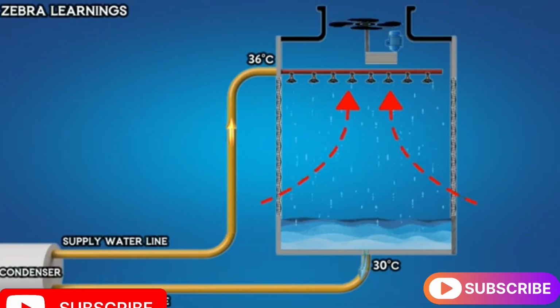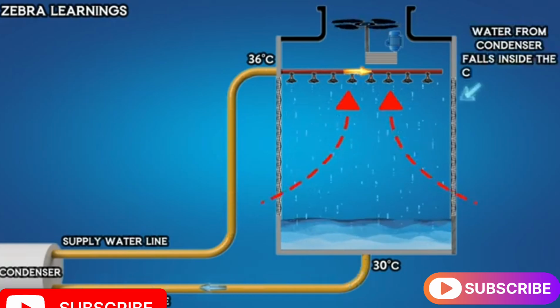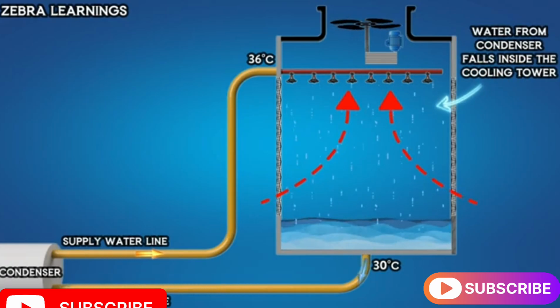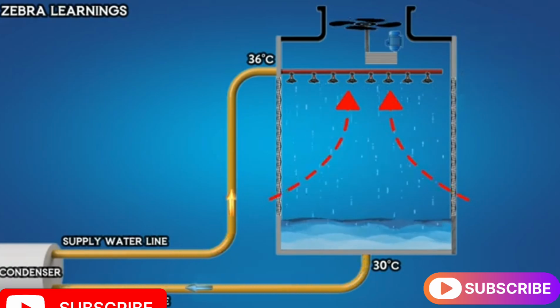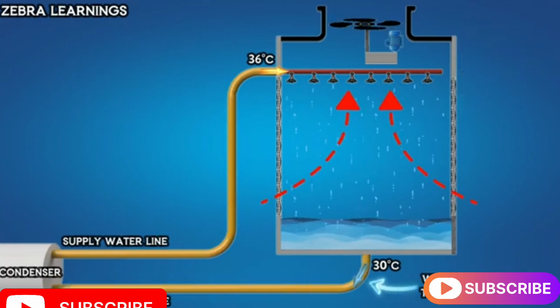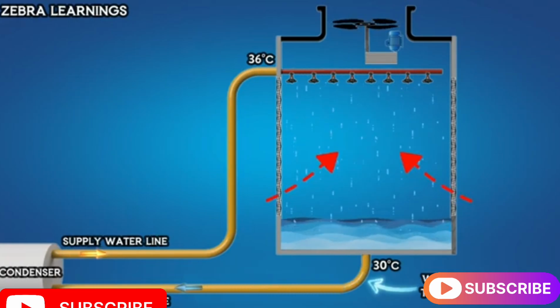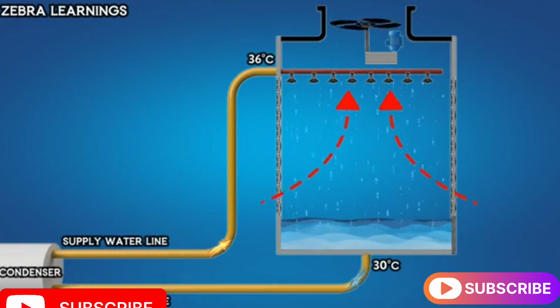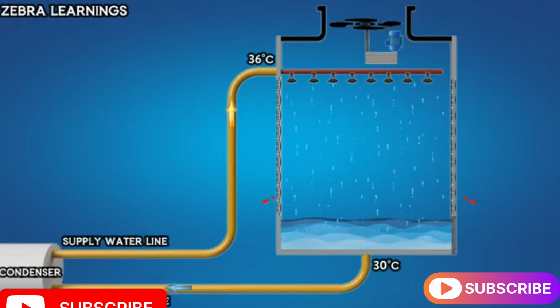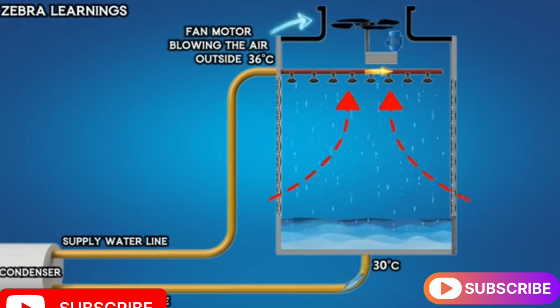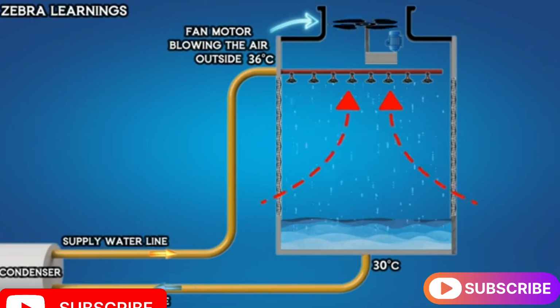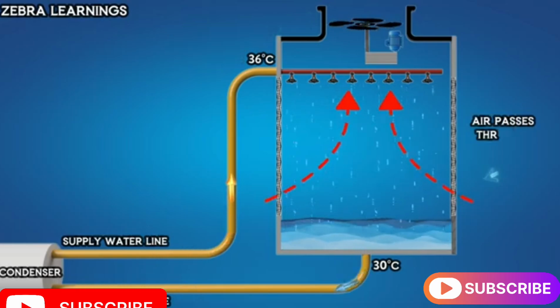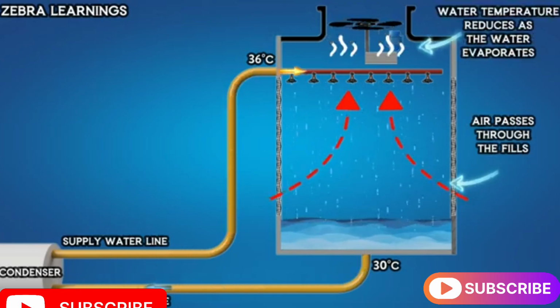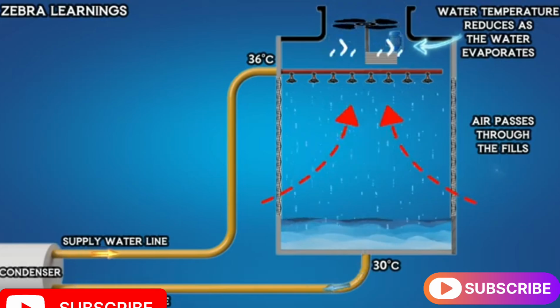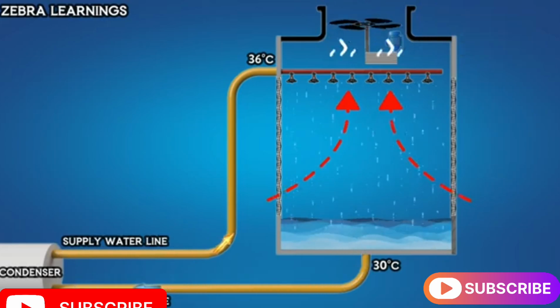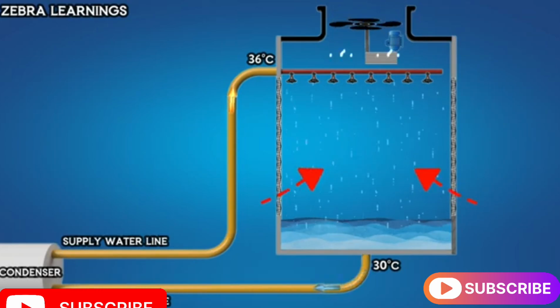In a cooling tower, water from the chiller's condenser falls onto the cooling tower fills and slowly travels downwards, then returns to the chiller's condenser through the return line. This water is used to reduce the temperature of the refrigerant in the chiller. The fan motor in the cooling tower draws air upwards through the fills. As the air passes through the fills, some of the water evaporates and is carried away by the air, cooling the water. This cooled water is then returned to the chiller.